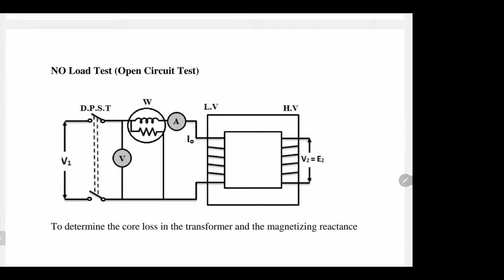Why prefer that? Because it's safe. It's better to deal with just the low voltage side, not to apply a voltage like 1,000 volts or 2,000 volts in the high voltage side. No, just leave it open and put all your measuring instruments at the low voltage side to be safe, only for safety reasons. Okay. You keep the secondary open, in this case the high voltage side.